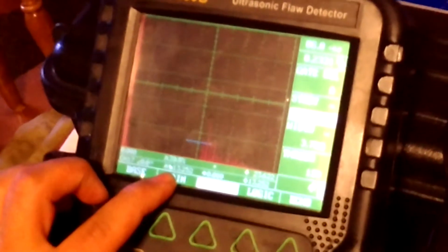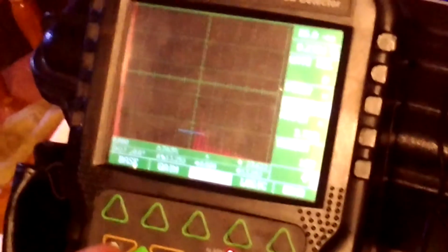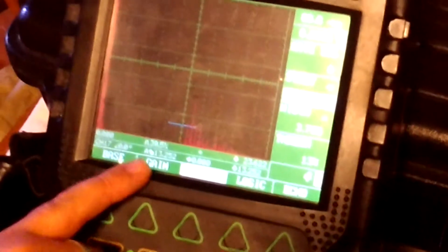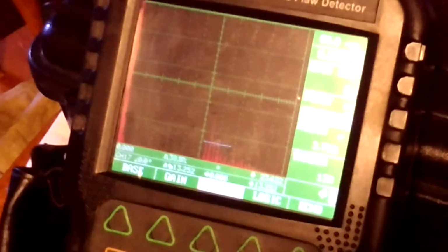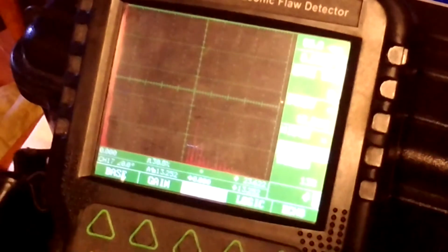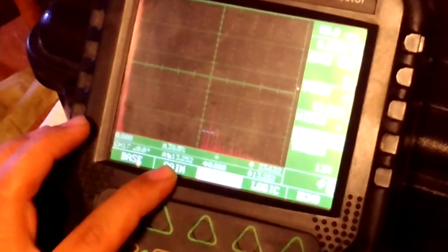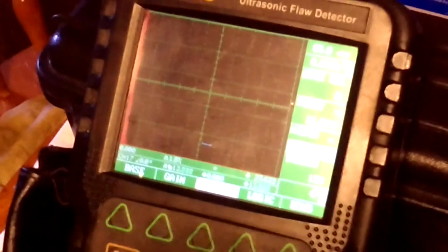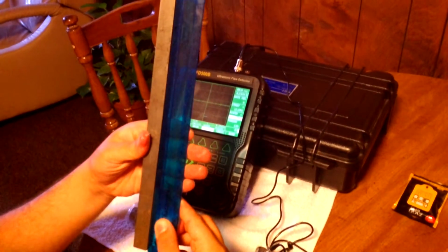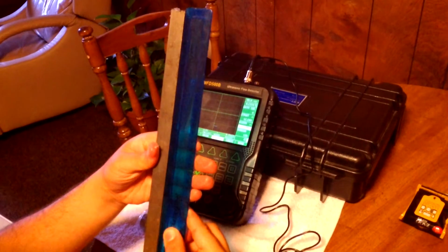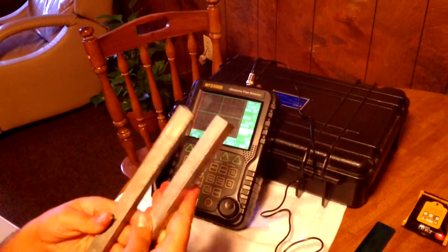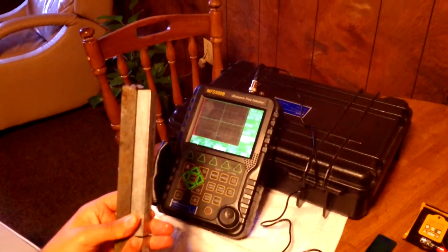Then this indication will tell me how long this steel bar is, because the first echo is the echo coming back from the end of the other interface of the bar, and this echo is indicating a length of the bar of 13 inches, 0.2. We can make sure that this is the correct length. I'll just make my gate smaller, and now it's saying it's 13.2 inches. Let's go ahead and measure that. So if I measure this, as you can see, it is about 13 inches in length.